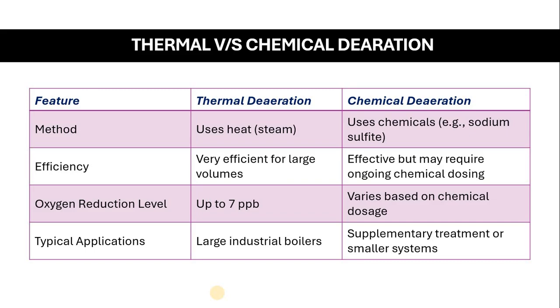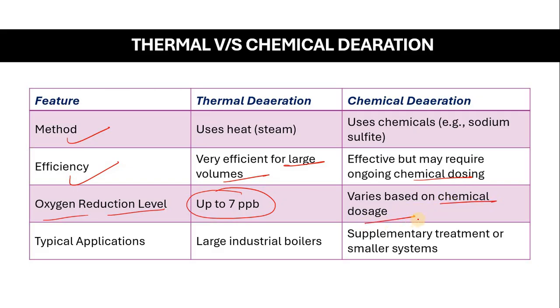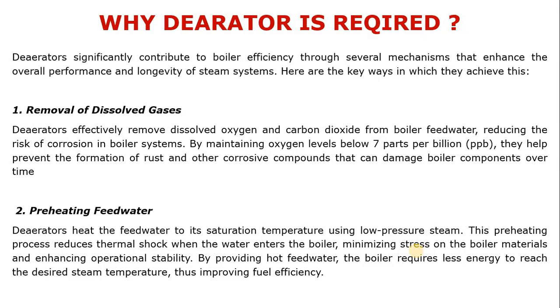Comparing thermal and chemical de-aeration: for large volumes, thermal de-aeration is preferred, while chemical de-aeration effectiveness depends on ongoing chemical dosing. In terms of oxygen reduction level, thermal de-aeration achieves down to 7 parts per billion, while chemical de-aeration depends on the chemical dosage as specified by the manufacturer. Thermal de-aeration is typically used in large industrial boilers, while chemical de-aeration is used as supplementary treatment or for smaller systems.